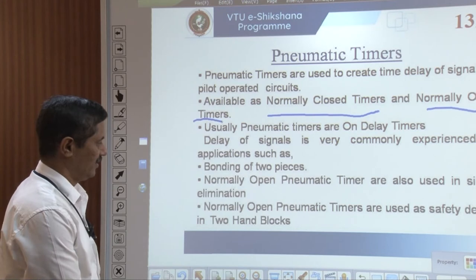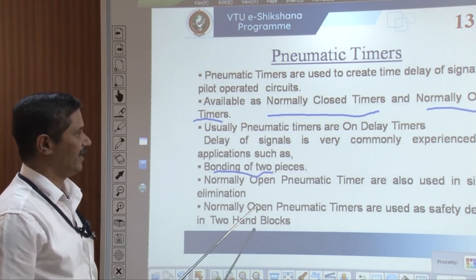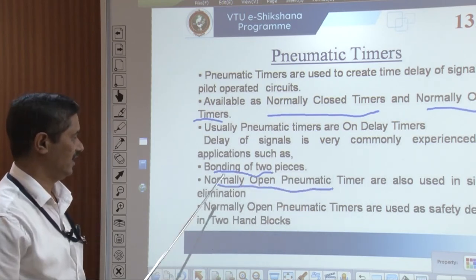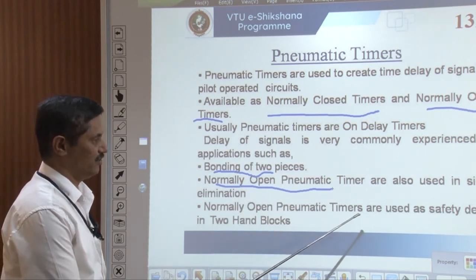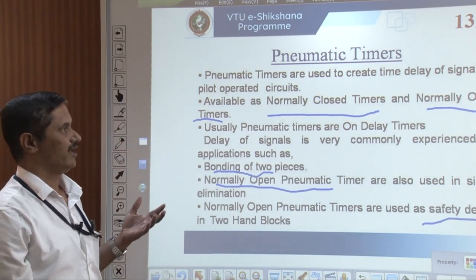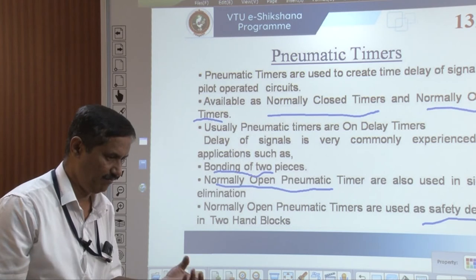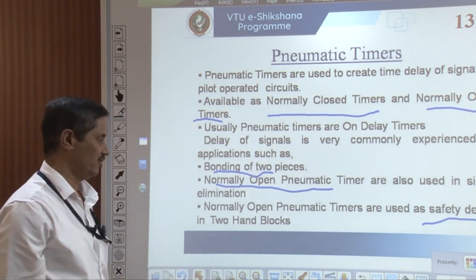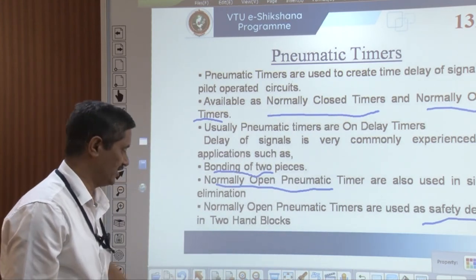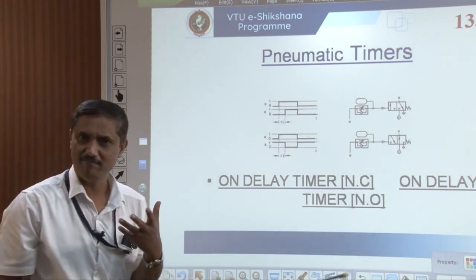Normally-open type can also be used in signal elimination — normally-open pneumatic types are used as safety devices. You can use a normally-closed or normally-open type of pneumatic timer. How these pneumatic timers look and are manufactured: it is a combination of a DCV valve with a pilot signal given through air as a signal to the DCV. However, the functionality involves allowing air through a small, precise control element — a precision flow control valve, not a normal flow control valve.